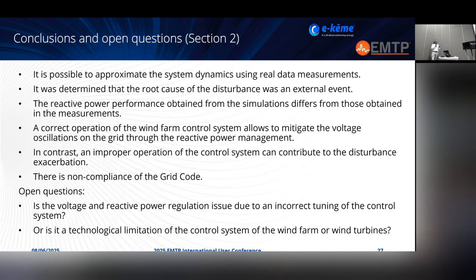We can also conclude that the wind farm was not able to regulate at a voltage set point, nor a reactive power set point. So there was no compliance with the grid code, and this could, as I said before, turn into sanctions, fines, or maybe loss of grid access for the wind farm. So there are some open questions. Is the voltage and reactive power regulation issue due to an incorrect tuning of the control system? Or is it just a technological limitation of the wind farm, or maybe the wind turbines?